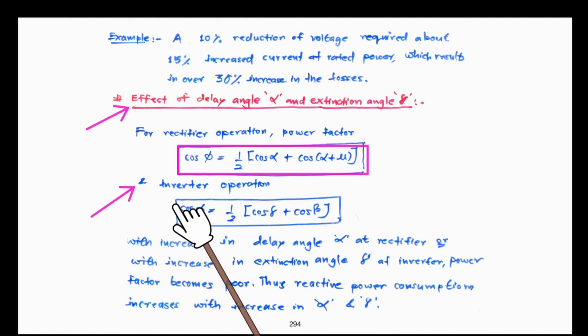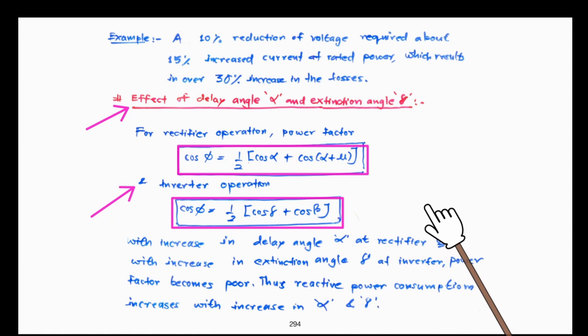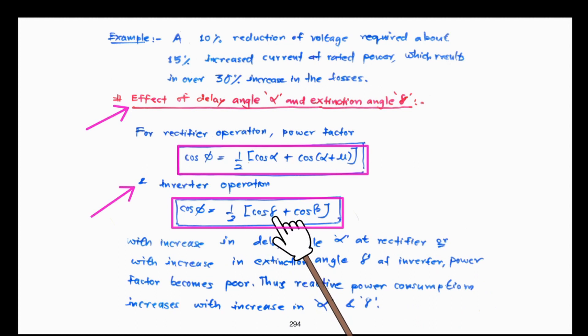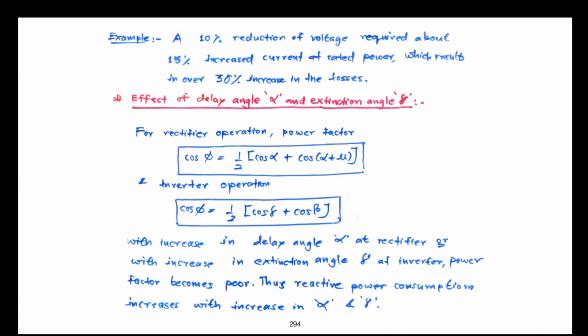Similarly, at the inverter end, the power factor equation is: cos phi equals one-half times (cos gamma plus cos beta). With variation in the extinction angle depending upon the operating conditions of the HVDC controller, gamma will keep varying and consequently phi will also vary. Since alpha and gamma always have some finite values even in steady state, the reactive power consumption always increases and is always required for the stable operation of HVDC converters.